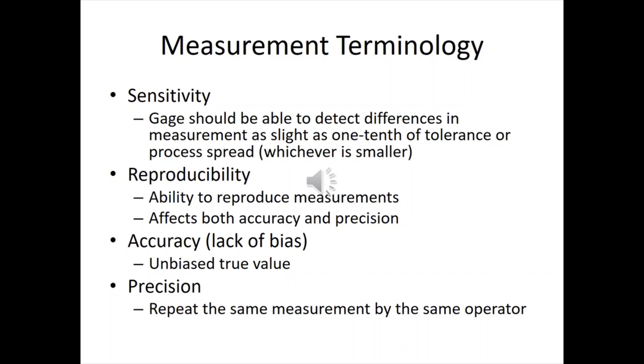First thing you need to know is sensitivity. You want your gauge to be able to detect differences in the measurement. Rule of thumb, about one-tenth of the tolerance or the process spread, whichever is smaller. So for instance, if you've got a one-inch tolerance, you want it to be one-tenth of an inch on your gauge.